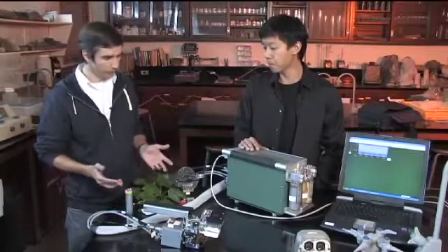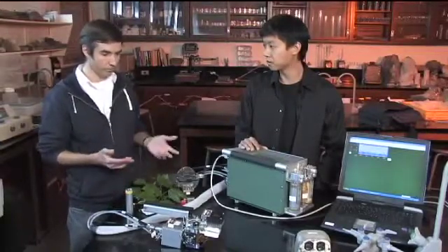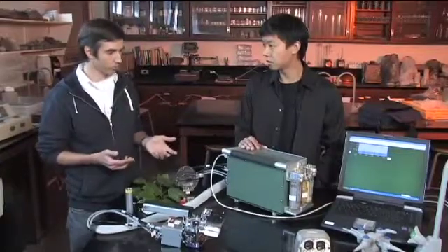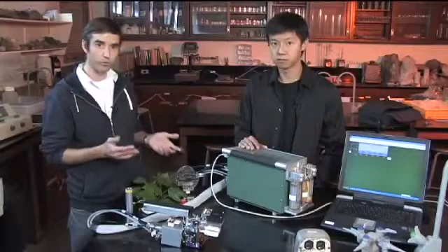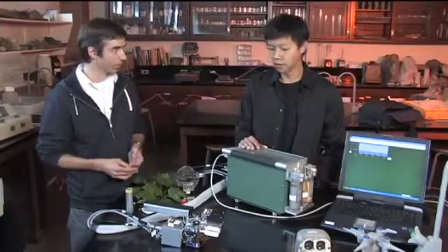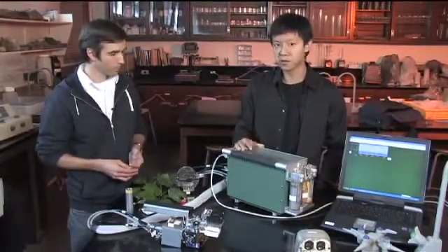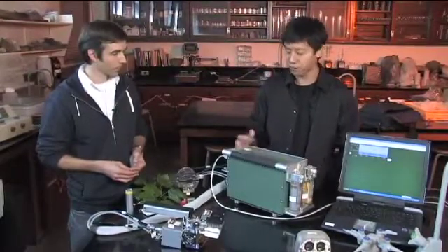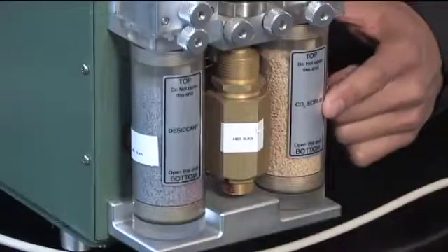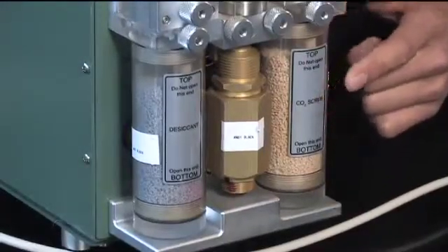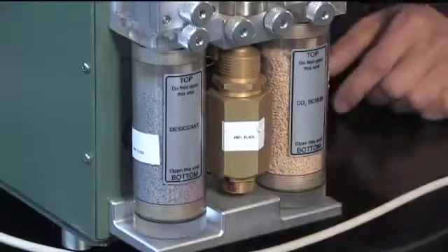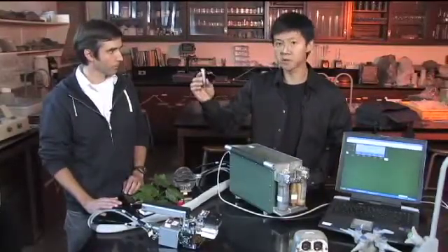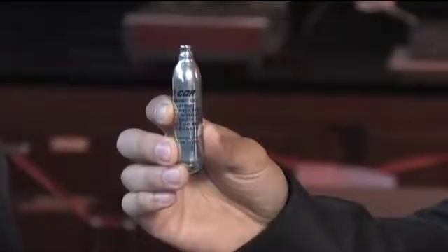I can see how we might be controlling temperature with the fans. But how do we actually control CO2 if the CO2 level in the chamber is fluctuating? The LICOR 6400 can control CO2 using two ways. It can reduce CO2 by using chemical scrubbers located on the side of the system here. And we have compressed CO2 gas in a 12 gram cylinder that injects CO2 into the chamber system.